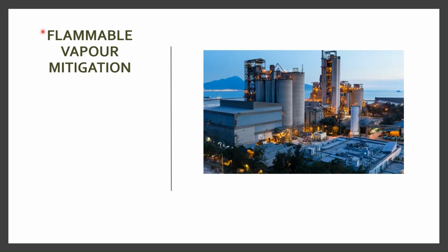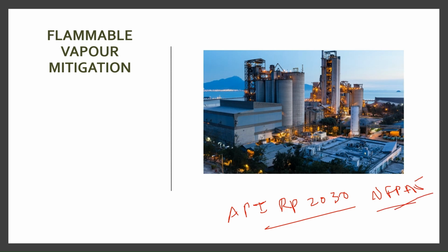Flammable vapor mitigation. This is an advanced topic. However, I will throw some light on this. For example, you have a power plant, and obviously sometimes there will be some gas or vapor leaks, and in order to prevent catastrophic fires in these scenarios, we need to use water spray systems as well. So fixed water spray systems are designed to control flammable vapors by mixing air with the water droplets in the spray cone, which helps dilute the vapor and reduce its flammability. Current standards like API RP 2030 and the NFPA 15 guide can be used in order to provide the water spray system. However, we don't have much information related to this.